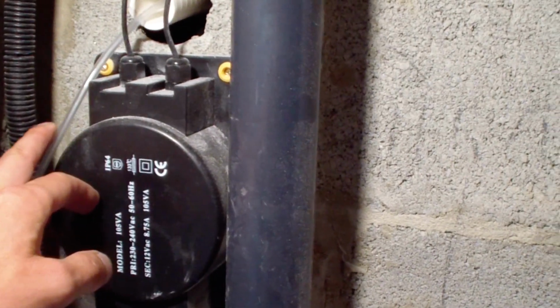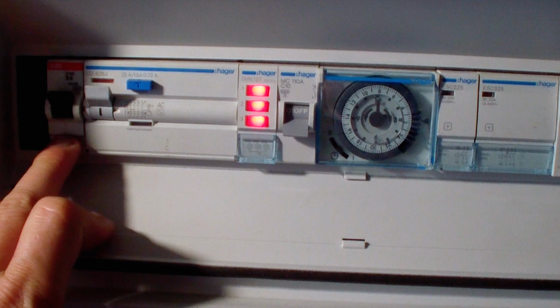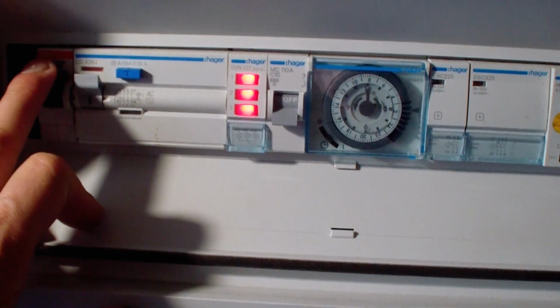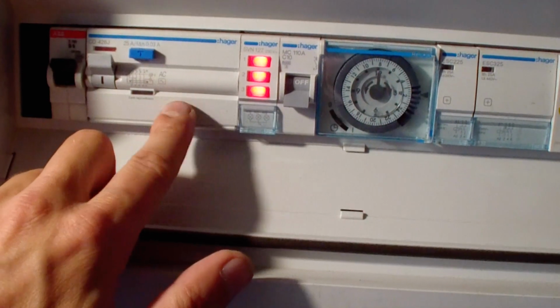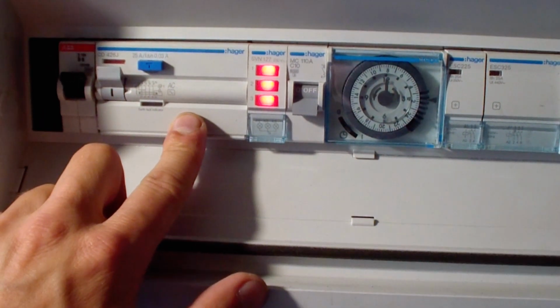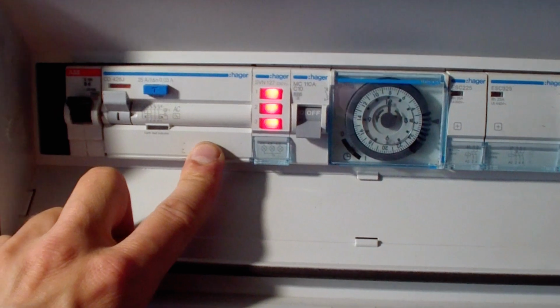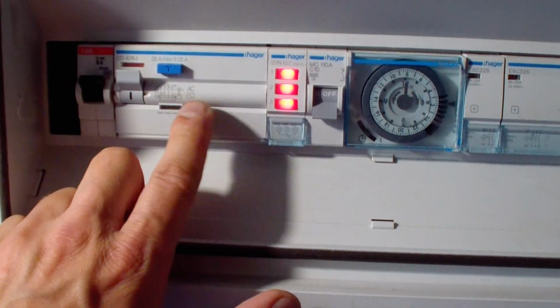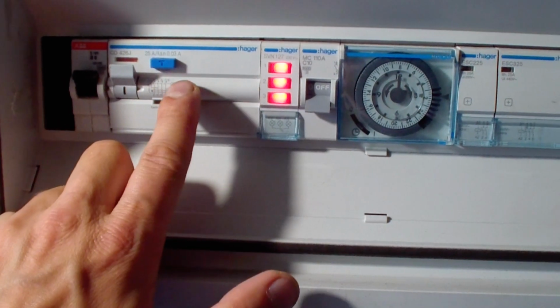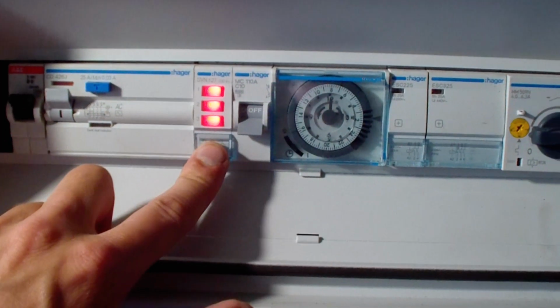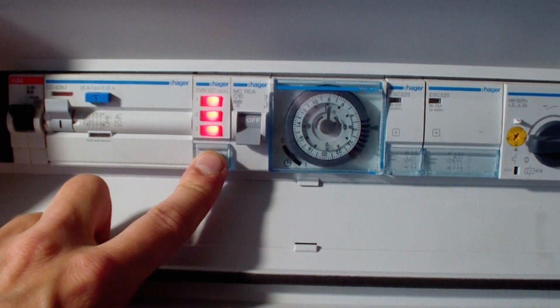This is the tube from the pneumatic button for the countercurrent. Let's see. This is the modular switch for the lighting. See? The light is off. And it is connected outside the residual current circuit breaker. This is done so that when the RCCB trips or we turn it off in winter, the plant room will always have light. Indicator light for monitoring the presence of 3 phases.